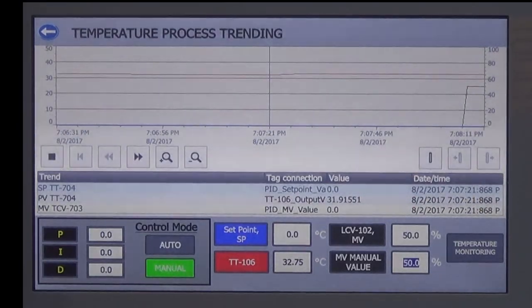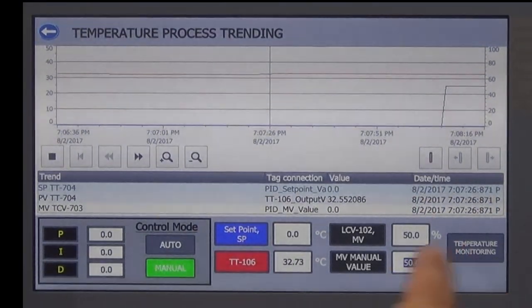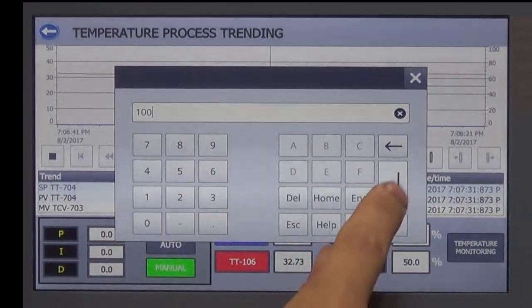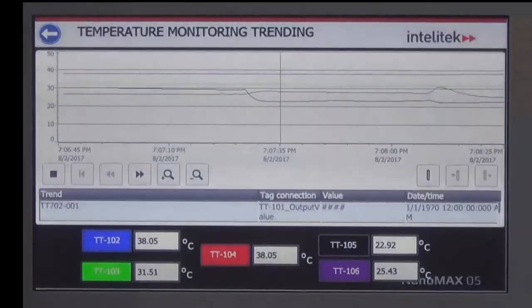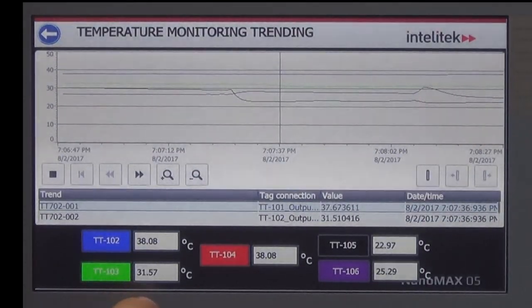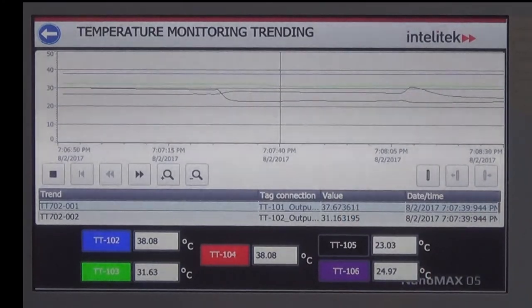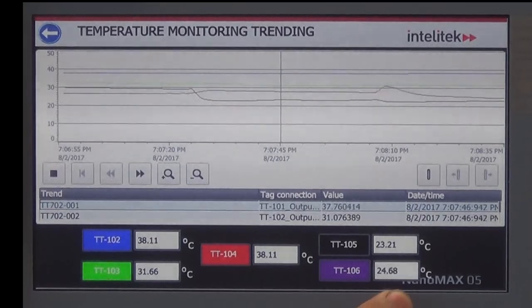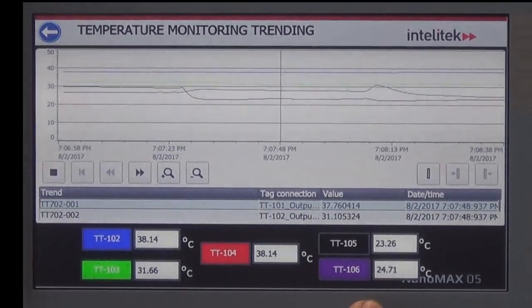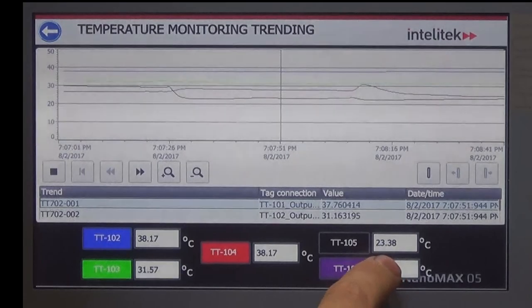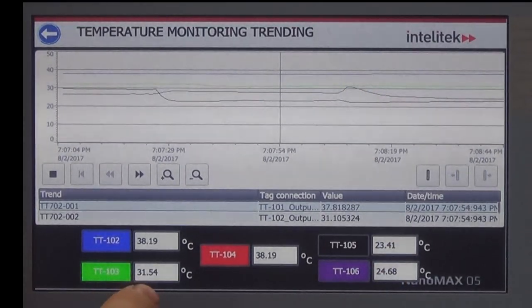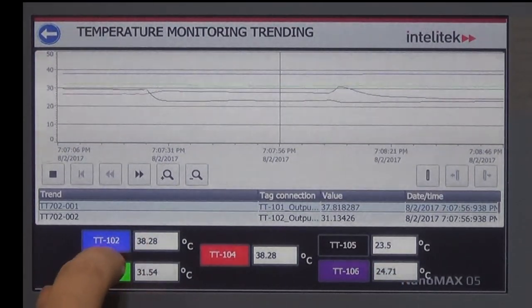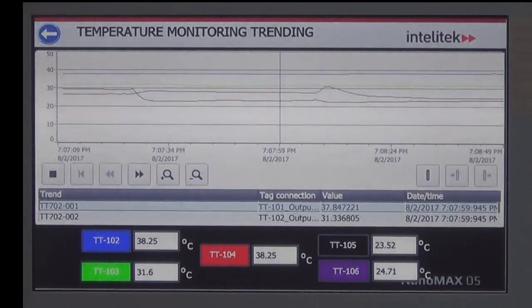And we can see that in this particular unit, we have an additional setting. And we can look at all the temperatures and the graphing of all the different temperatures. So we have the various sensors on the system, and we can see the value at the valve, which is TT106. We can see the hot water entering the system, which is entering in at 23. And then we can see the two temperatures at TT102 and TT103, which are the two side entrances from the cold water tank.